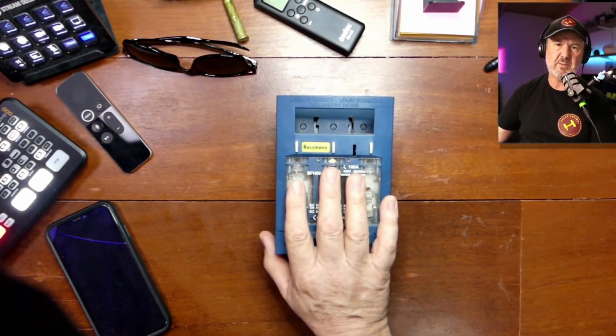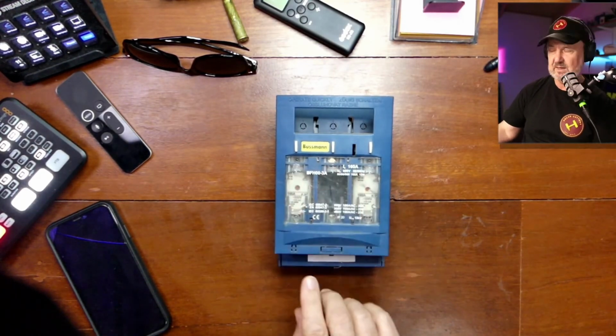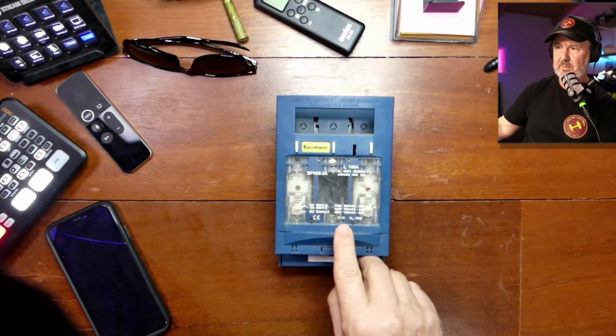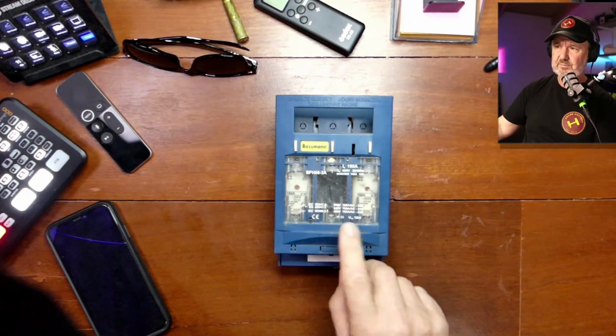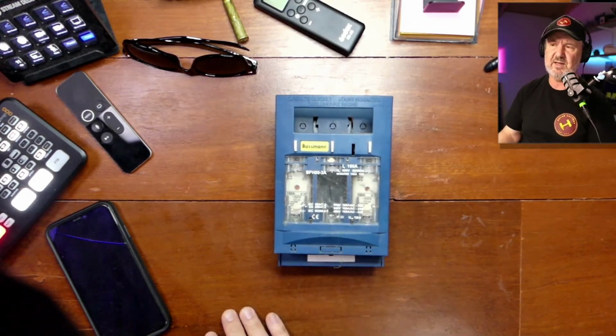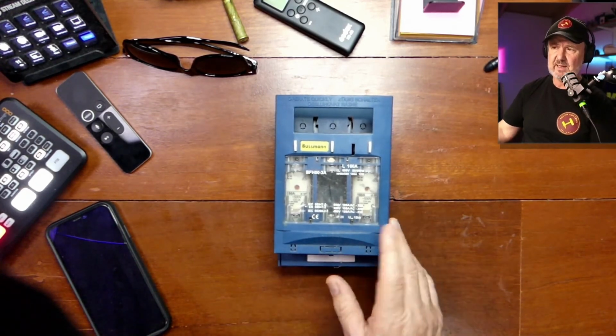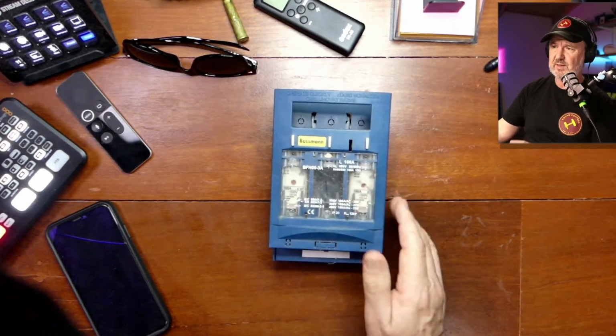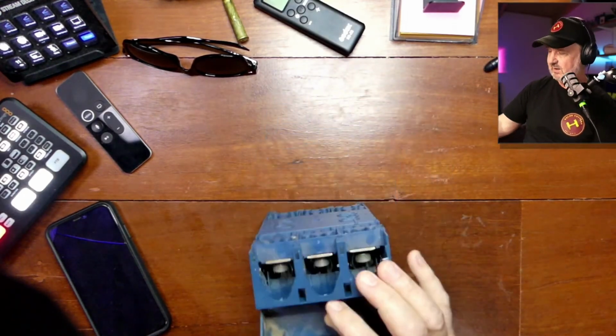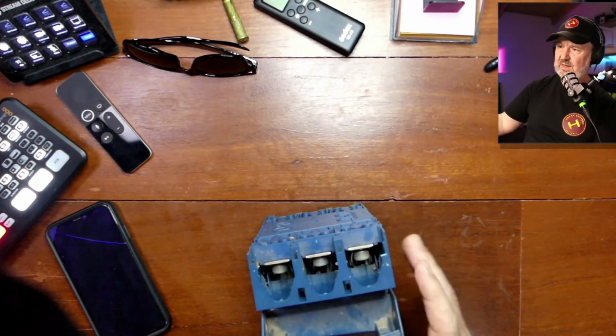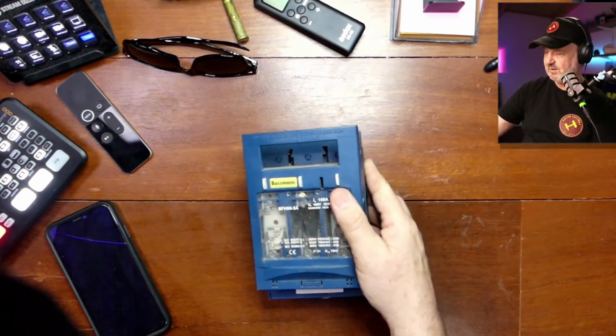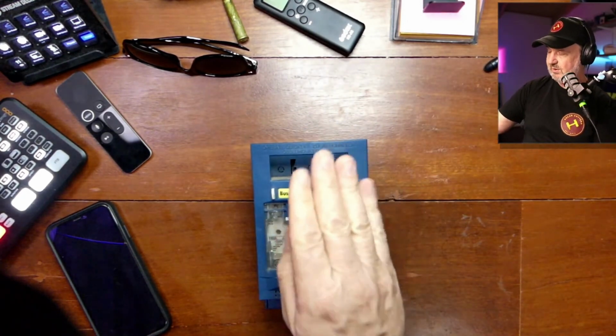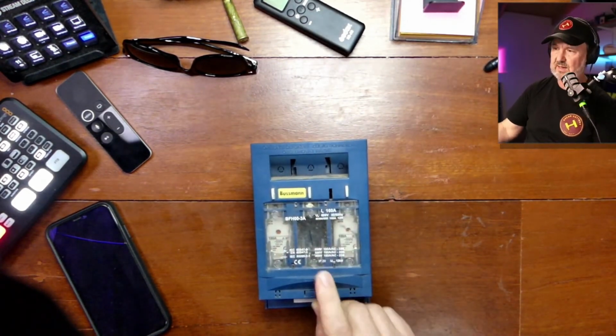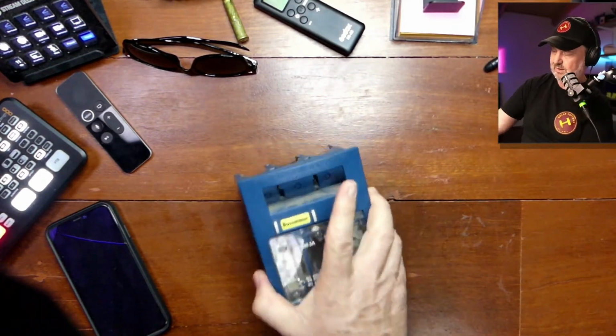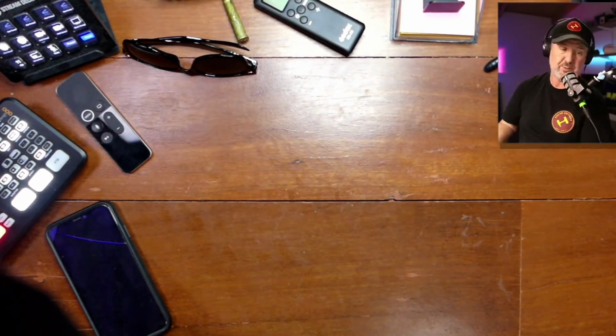But the big problem we're having now is that the new battery standard mandates that DC isolators used indoors for battery systems need to be IP23 as a minimum. Written on the front here is IP20, so this doesn't comply because of its IP rating. Used in circuits below 60 volts, access of live parts is acceptable at IP2X, but once you go to IP23, it's about dust and other environmental ingress, so you need something with a proper rating.